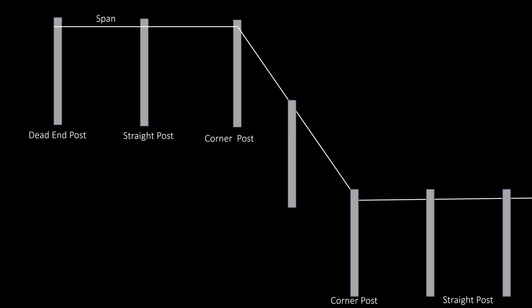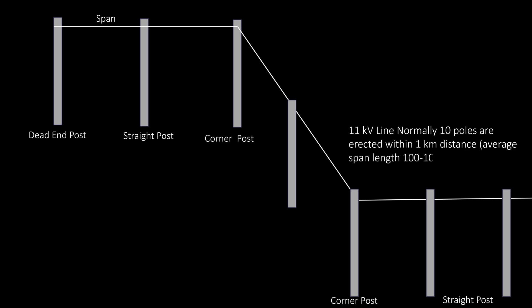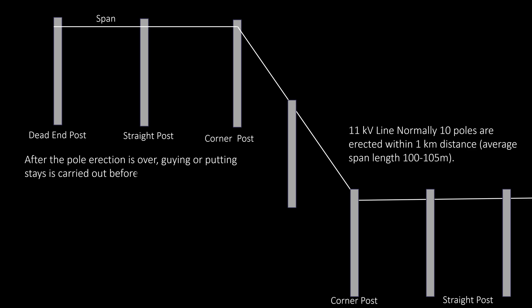We first erect poles at suitable positions as per proper survey and drawing. For 11 kV lines, normally 10 poles are erected within 1 km distance, with an average span length of 100 to 105 meters. After erection of poles, guying or putting stays is carried out before fitting and fixing of other accessories like cross arm, channel, V-bracket, insulators, etc.